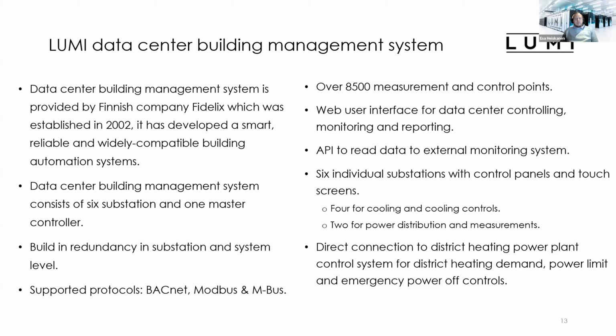And we also have a direct connection to the district heating power plant in the area. The control system tells us real-time information about the district heating network from the city of Kajaani, how much district heating demand there is. Based on that demand, they can set us a power limit, how much heat we can produce to the district heating, and they can tell us to emergency power off our district heating in case there are some issues in the district heating network.